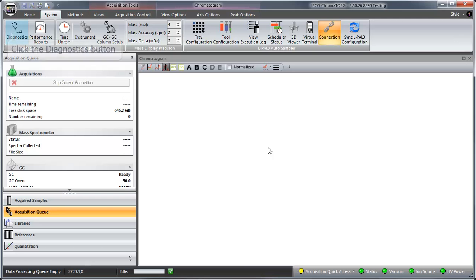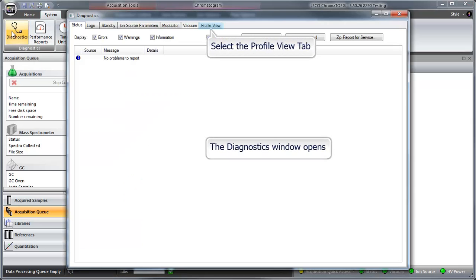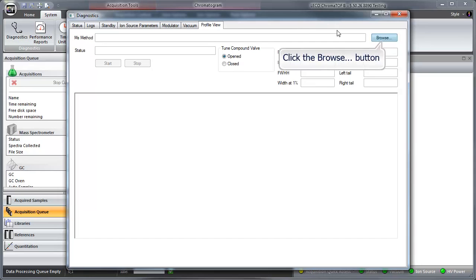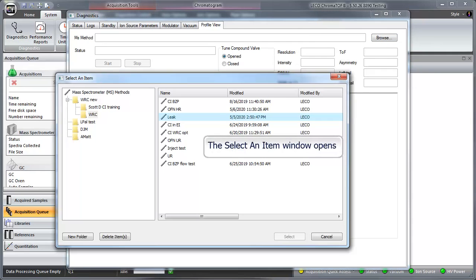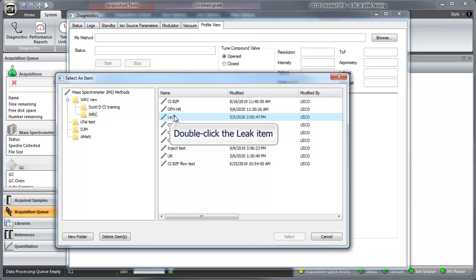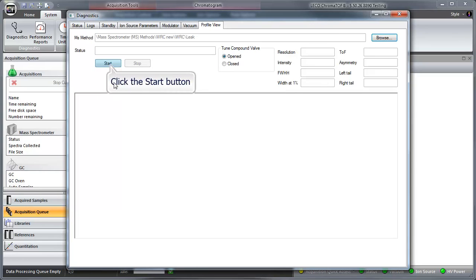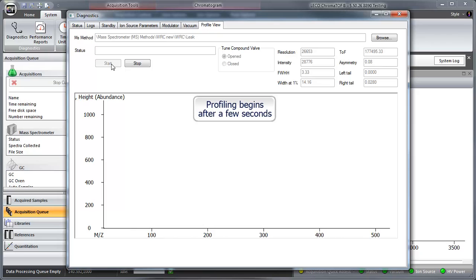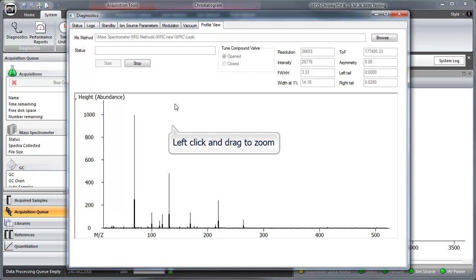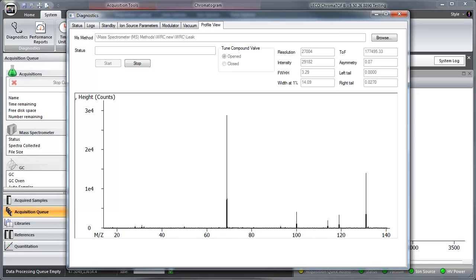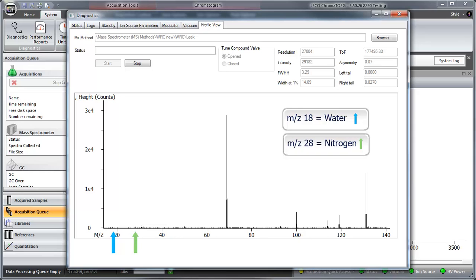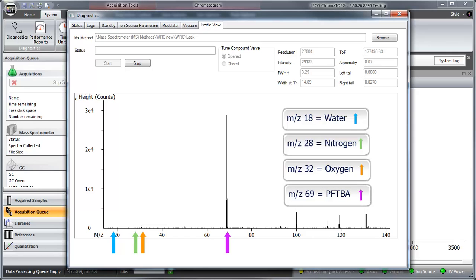Once a method has been created, enter Diagnostics and access the Profile tab. Select a method using the Browse button and hit Start to begin profiling the instrument. The masses to monitor for a system leak are mass to charge 18, which identifies water, mass to charge 28, or nitrogen, 32, or oxygen, and mass to charge 69, which is the reference peak of PFTBA.